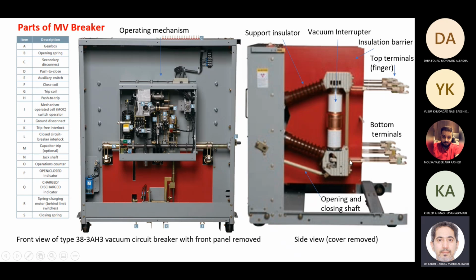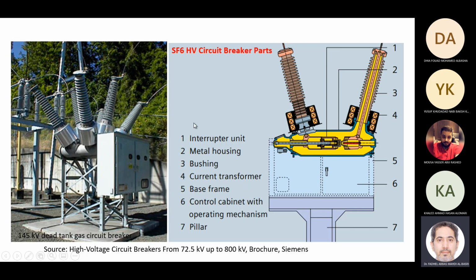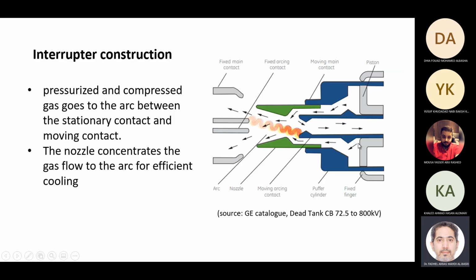This is the insulator. So the breaker is connected to the terminals, this is it. So this goes to one terminal of the breaker, and current flows this side, outside. So these are the terminals. For medium voltage, and high voltage breakers, this is the interrupting chamber. Okay, these are CTs, and this is the insulation medium. Inside here could be a gas.